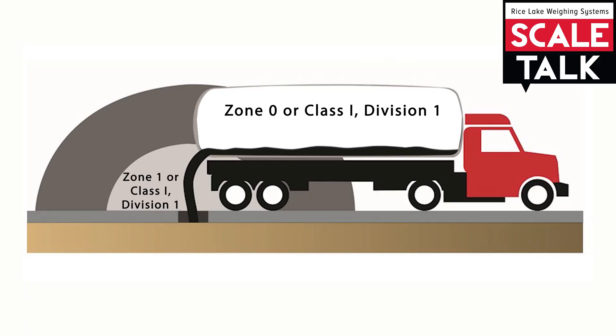Outside the truck in the lighter gray area we have zone 1 division 1. This is where it can get a little tricky, because this is a zone 1 area in Europe and Asia, but it's still considered class 1 division 1 in North America with the same protection required as the zone 0 equivalent. So depending on your location, the required protection method might be different. In North America it would require the highest level of protection, the same as inside the tanker, but other parts of the world are not quite as strict as this is one level down for maximum protection. This area is typically where a load cell or indicator would be mounted.